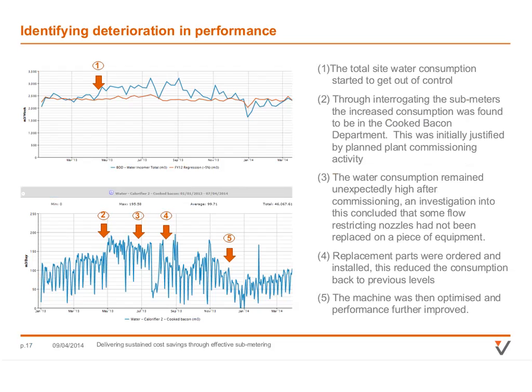Once the machine was finished commissioning, the fault was still there, so we started investigating further. We found that some restriction flow nozzles weren't working properly. We fitted some new restrictors, and it made some big differences.